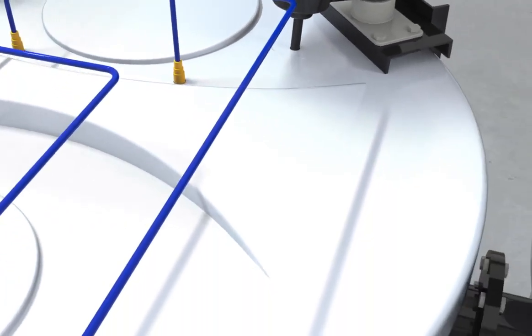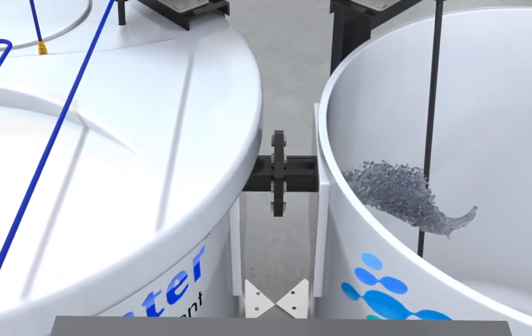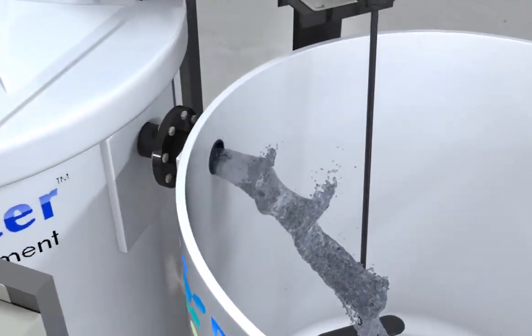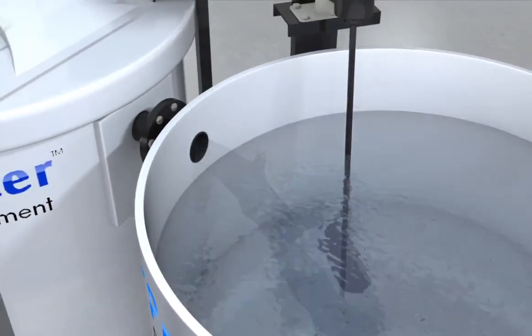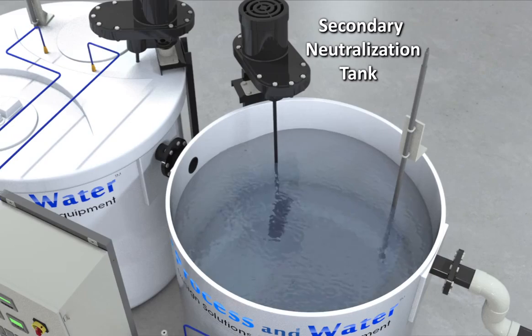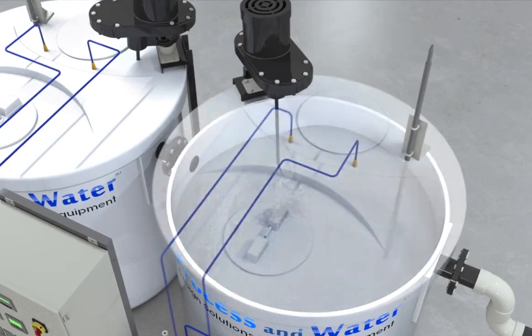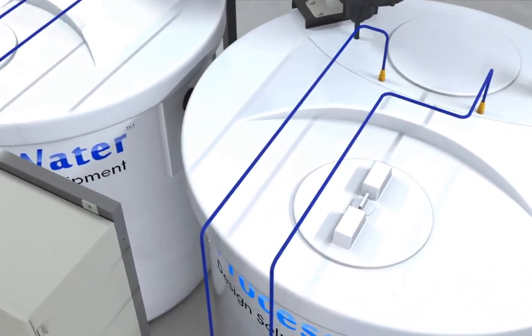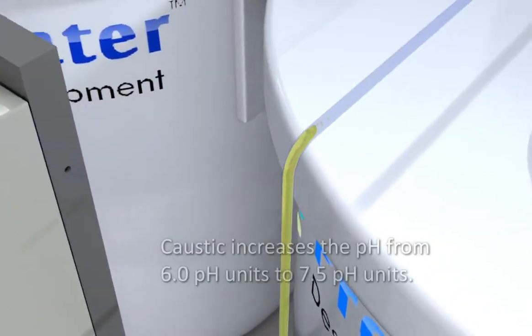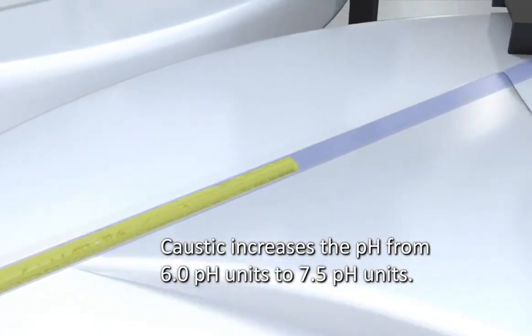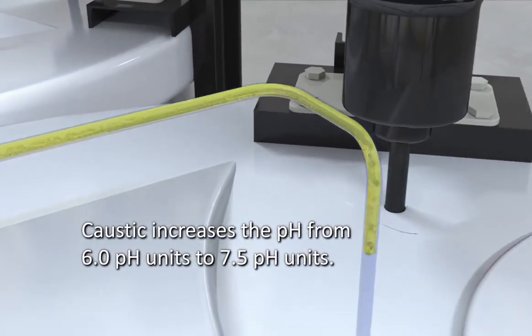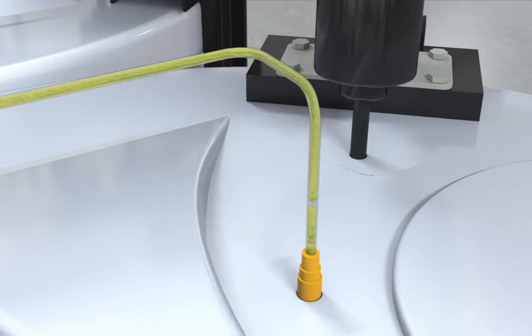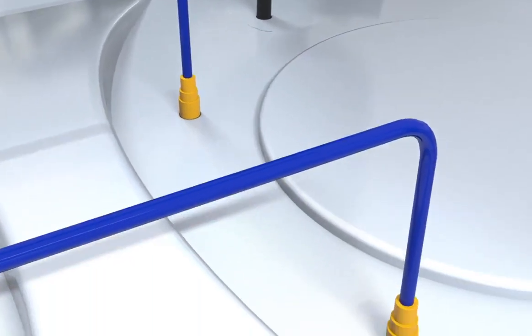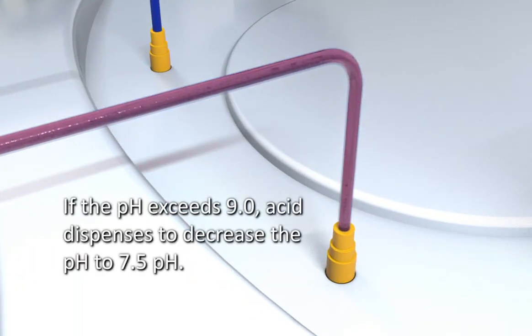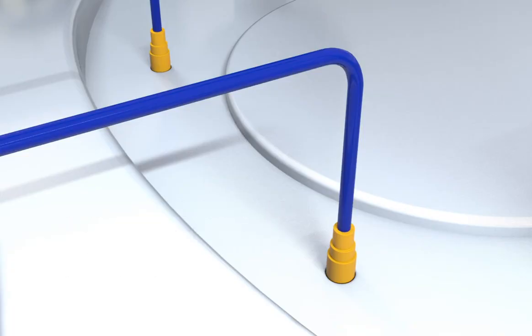As the water solution mixes together, it eventually cascades from stage 1 pH to stage 2 pH, where the mixer continues to agitate the solution within tank 2. The second caustic metering pump feeds the chemistry once again to increase the pH from the 6.0 pH units to 7.5 pH, and if the pH should increase more than desired to over 9.0 pH units, then the acid pump feeding this tank will feed acid to decrease the pH to 7.5 pH units.